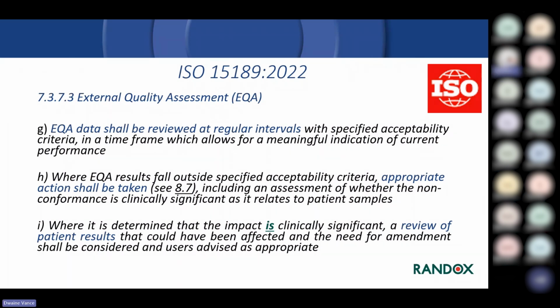Where EQA results fall outside specified acceptability criteria, then appropriate action shall be taken, including an assessment of whether the non-conformance is clinically significant. Where it is determined that the impact is clinically significant, a review of patient results that could have been affected and the need for amendment shall be considered.